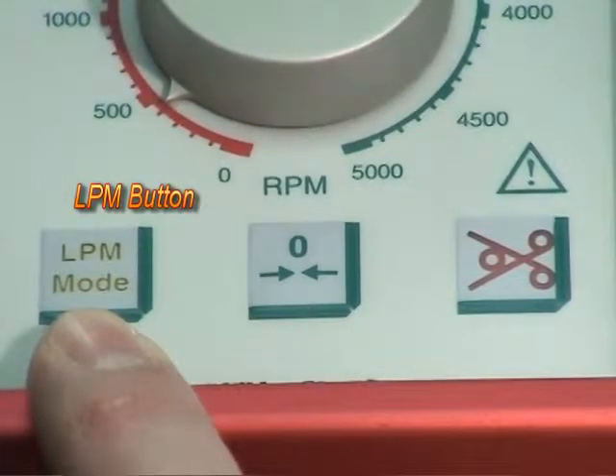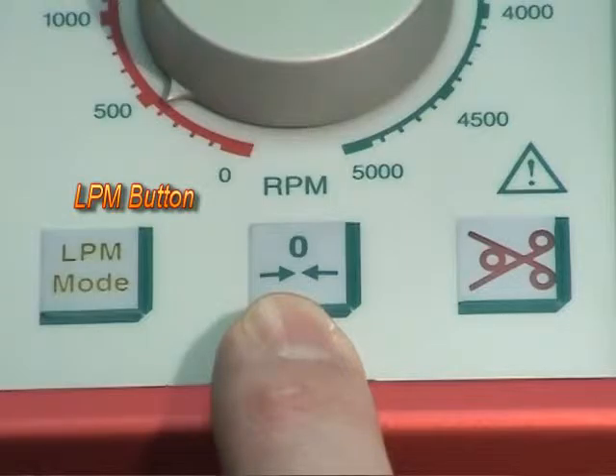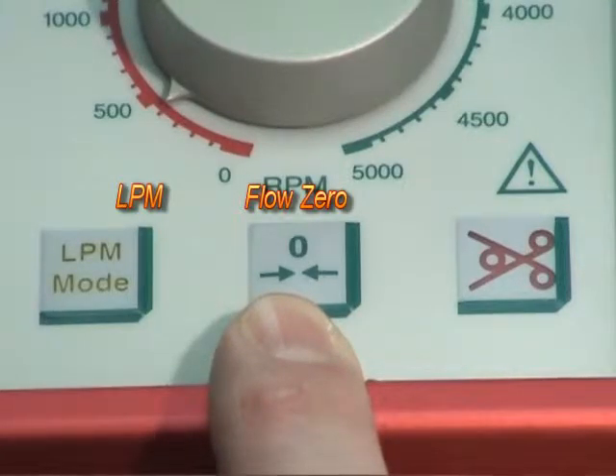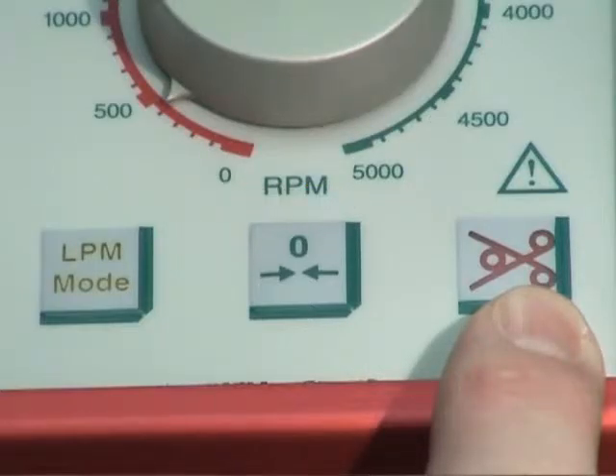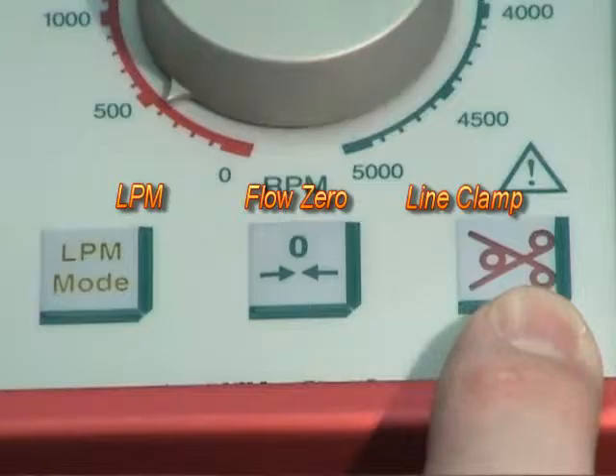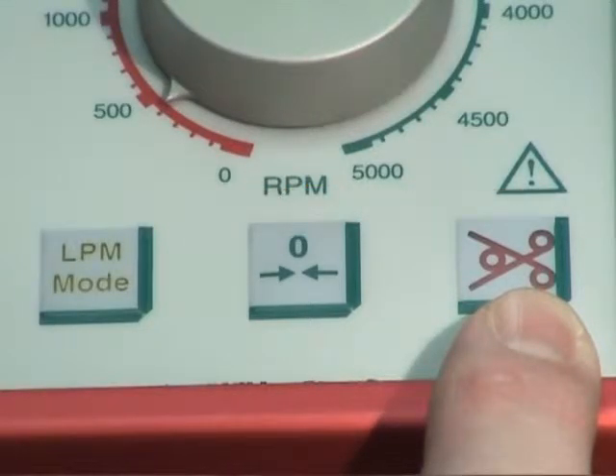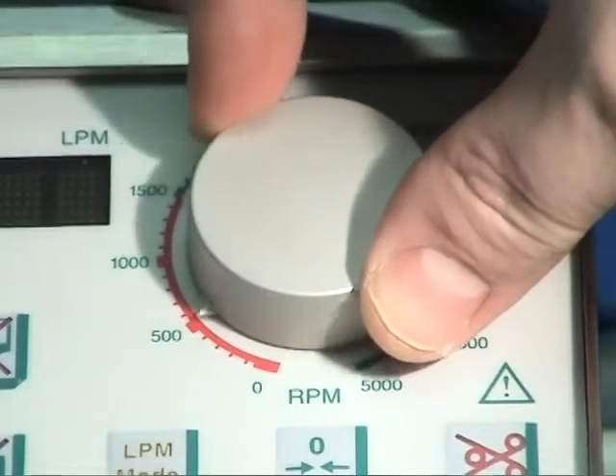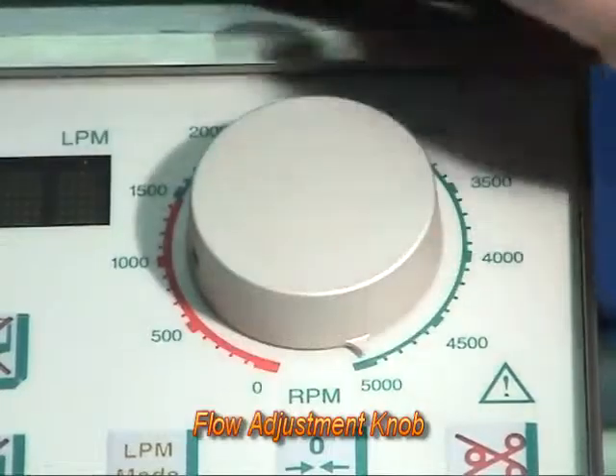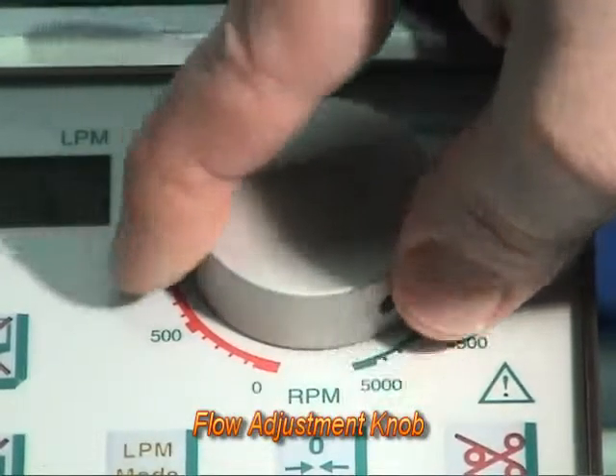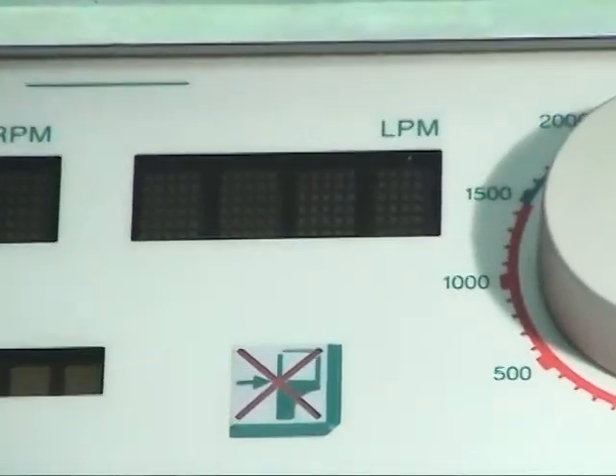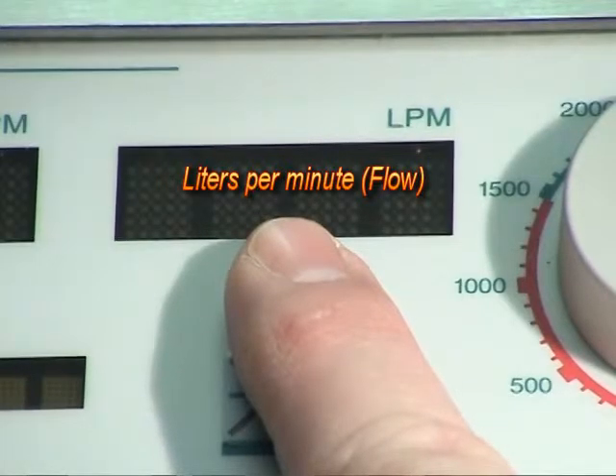The liters per minute button activates the servo regulation mode of the pump. The Flow Zero button calibrates your zero. The line clamp or valve confirmation button confirms the presence of a one-way valve or clamp to prevent retrograde flow. The flow adjustment knob adjusts pump speed by changing RPMs. Also note the gross speed RPM scale and analog scale for if the RPM display fails. Finally, we come to the liter per minute display, which displays flow in liters per minute.